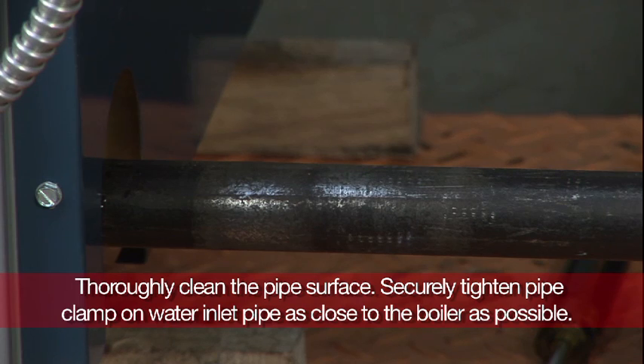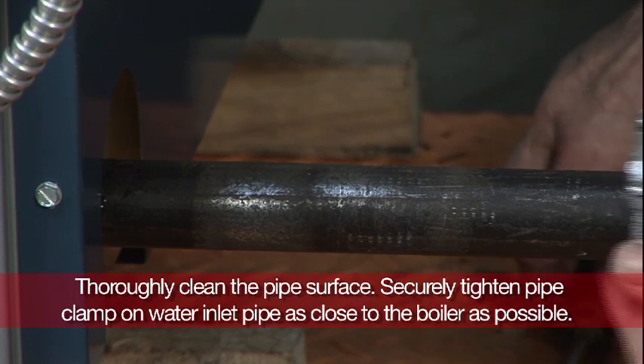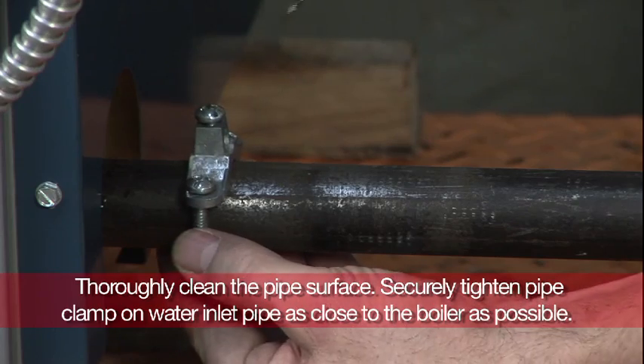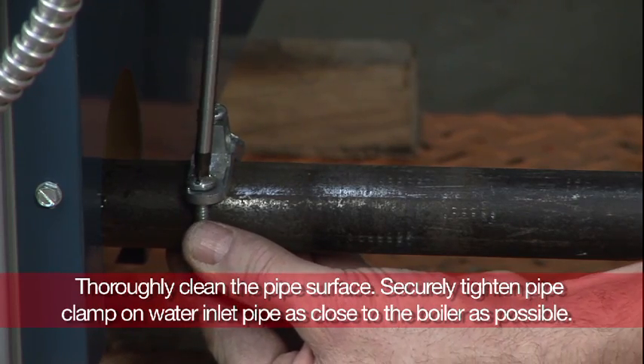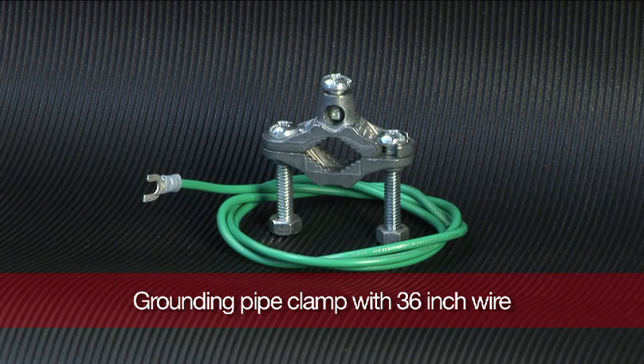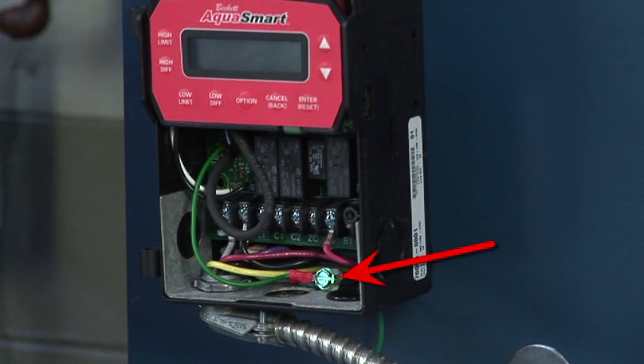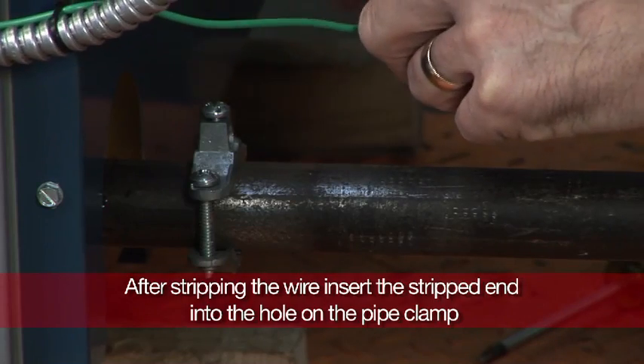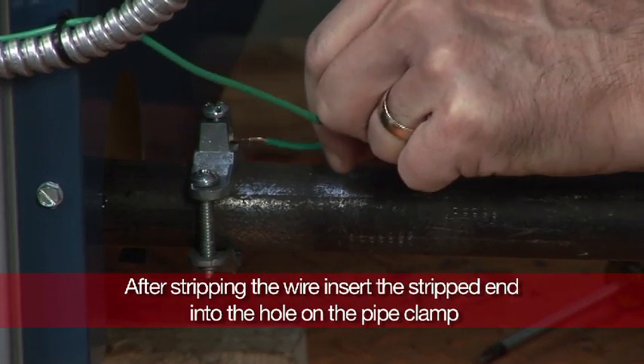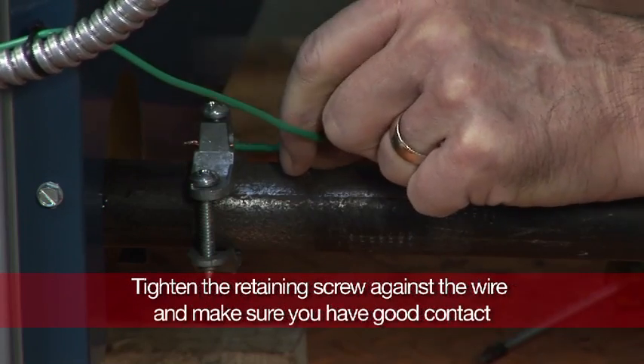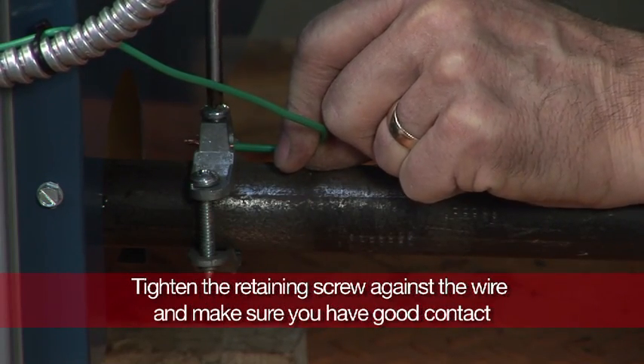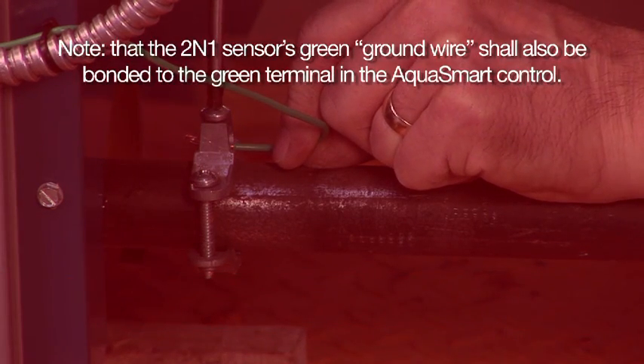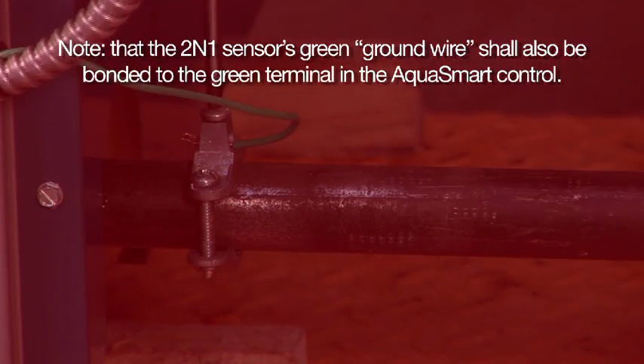Next, thoroughly clean the pipe surface. Then securely tighten the pipe clamp on the water inlet pipe as close to the boiler as possible. For the AquaSmart, we recommend that a grounding pipe clamp be mounted to the water inlet pipe and that the 36-inch green wire be bonded from the pipe clamp to the green terminal inside the AquaSmart control. After stripping the end of the wire, insert the stripped end into the hole on the pipe clamp. Tighten the retaining screw against the wire and make sure you have good contact. Note that the 2-in-1 sensor's green ground wire shall also be bonded to the green terminal in the AquaSmart control.